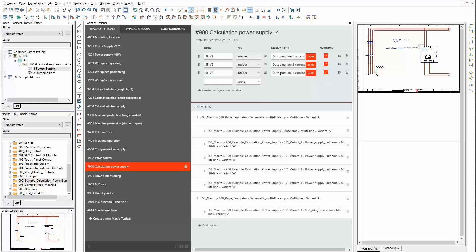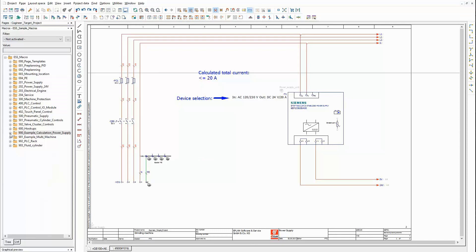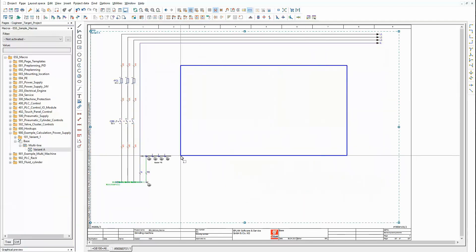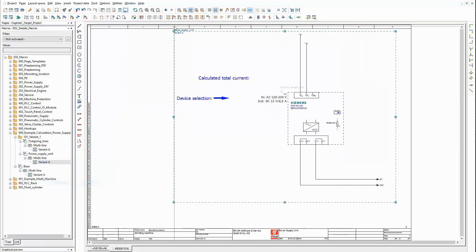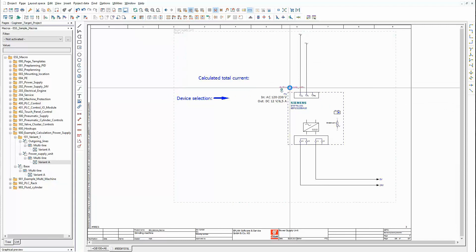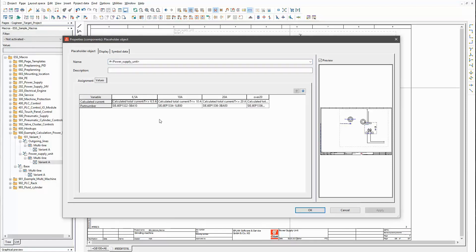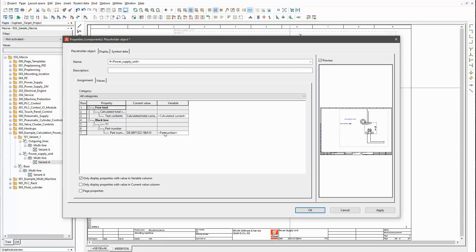Now let's have a look at the macros and their placeholder objects. I close the designer and expand the view of the macro navigator in the ePlan platform. This is the macro that contains the basic schematic for the power supply. As you can see, the power supply unit is missing — it's part of the next macro. And there is the first placeholder object. You have to use this syntax for the name of the placeholder object to make it available in ePlan Cogineer. The placeholder object contains four value sets, one for each possible power supply unit. The variables of the value set are connected to properties of the macro. The first one is the part number, and the second one is a free text property that is used to indicate the calculated current in the schematic.